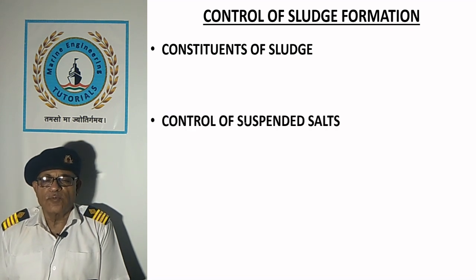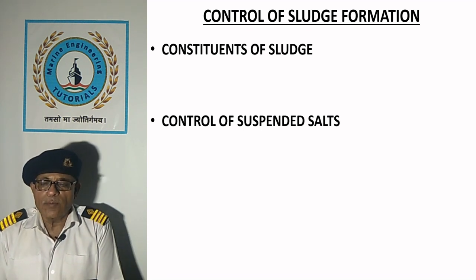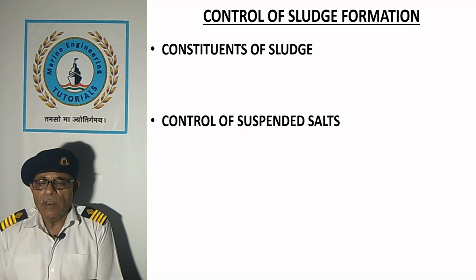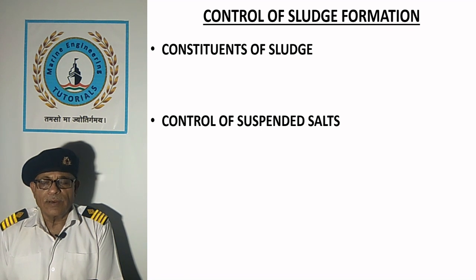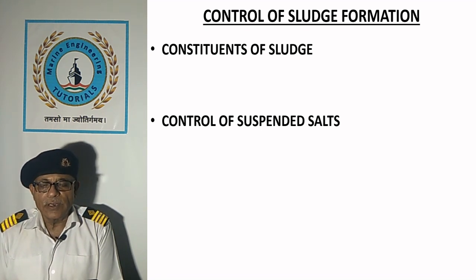Control of suspended salts: salts such as sodium chloride, magnesium chloride and magnesium sulphate are highly soluble in water, but their concentration in boiler water should be kept within limits by partial blowdown at regular intervals to prevent carryover or sludge formation. Sodium carbonate and sodium sulphate formed in the chemical reactions contribute to alkalinity in boiler water.